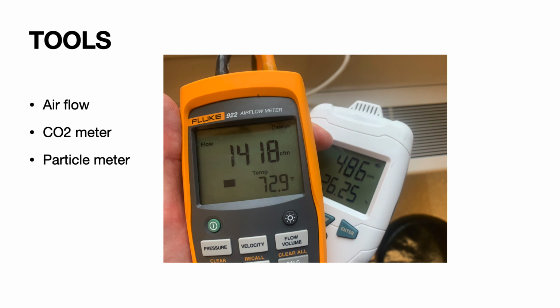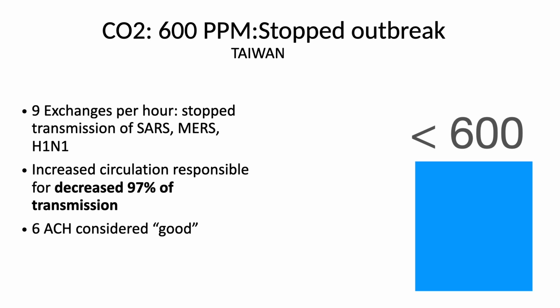For instance, this morning in Morrisville, we found a room with a little higher levels, still not unsafe, but it didn't seem like the ventilation system was working. We measured it, and sure enough, it wasn't. And we're also getting a particle meter to make certain that the HEPA filters are taking all the particles out.